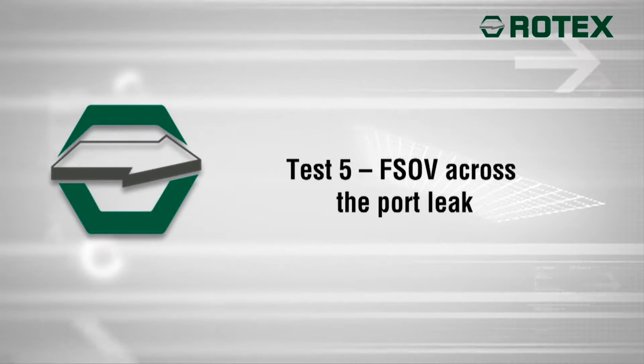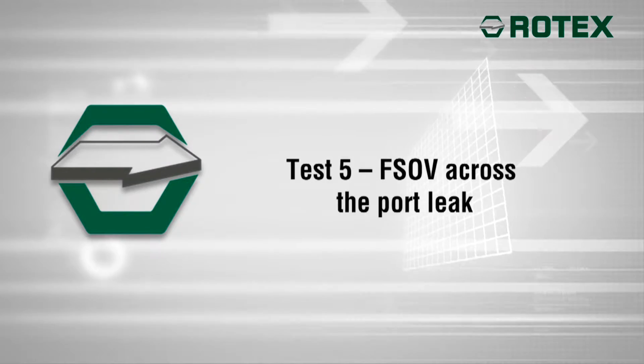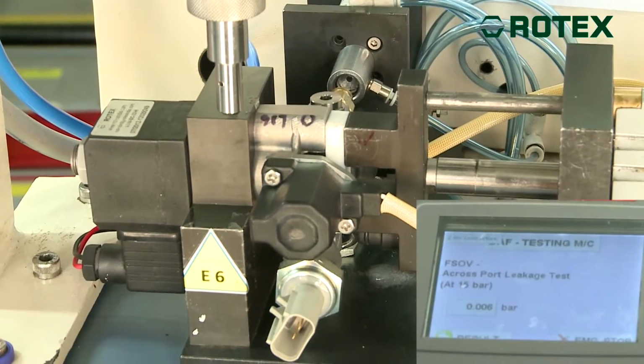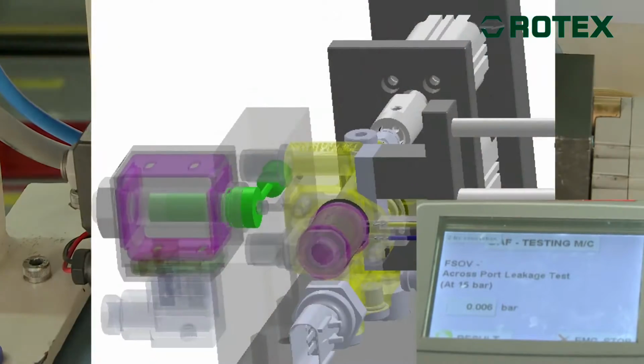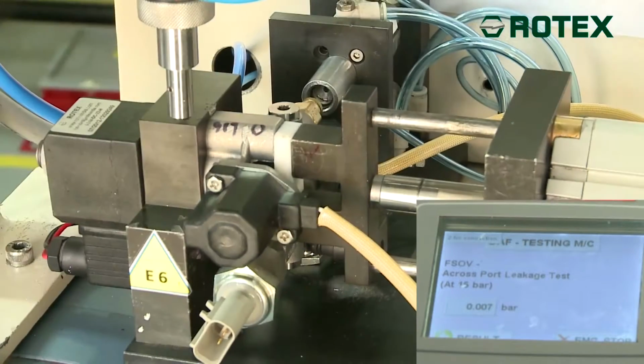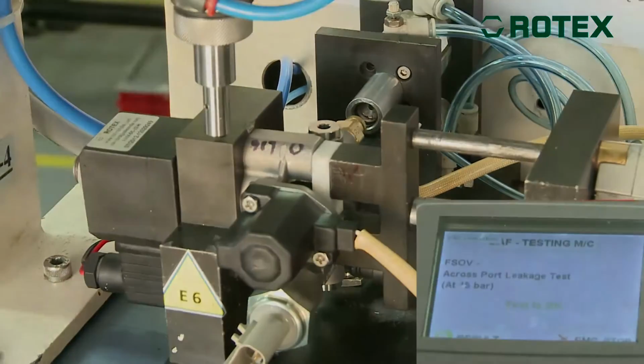Test 5. FSOV across the port leak. 12 bar air pressure is applied through fuel inlet port. For 30 seconds, pressure decay at the inlet side is measured to calculate the leak.